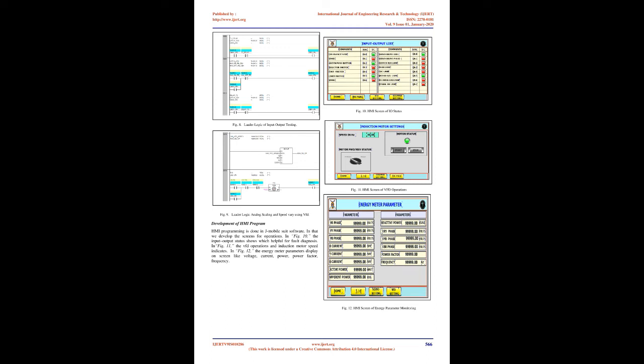In Fig. 1, all the inputs are connected to the PLC and the information will be sent to the PLC through it. The output devices are connected to the PLC outputs and driven from the input sensors and from the PLC program. PLC outputs will give the command to the frequency drive, and the drive will vary the frequency and the voltage to the induction motor. The speed will be varied from the drive. The energy meter is connected to the PLC through RS-485 communication and the data parameters will be read by the PLC through this communication. The HMI will be connected to the PLC, and information will be displayed or commands will be given for the operations from it.